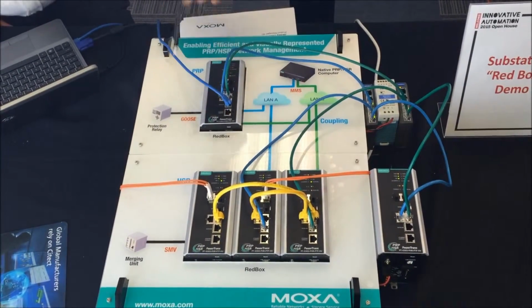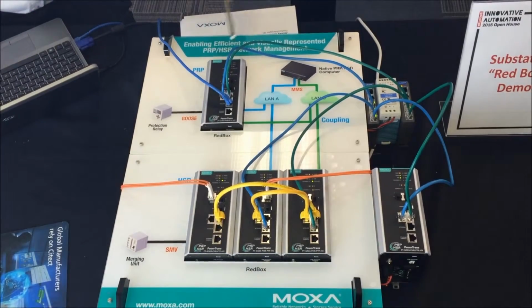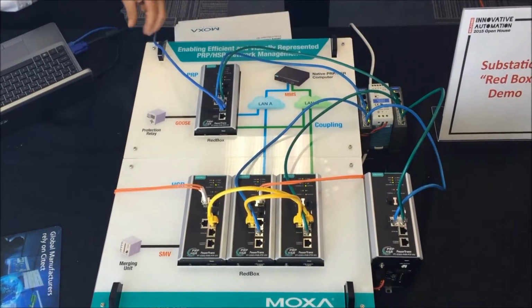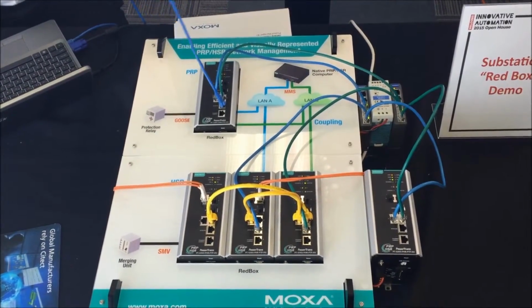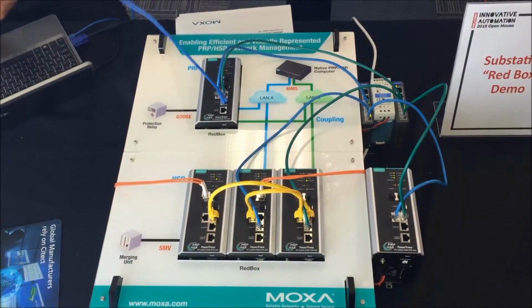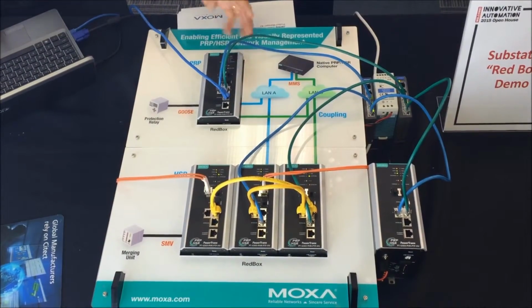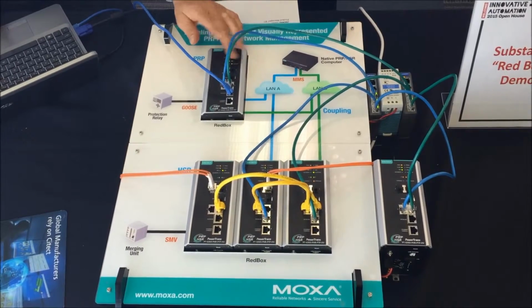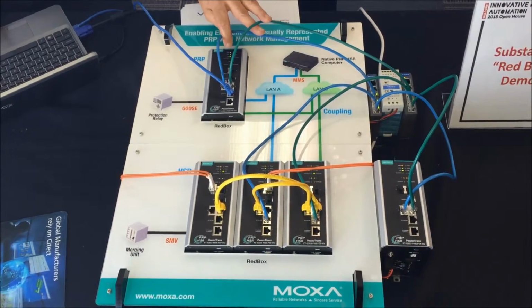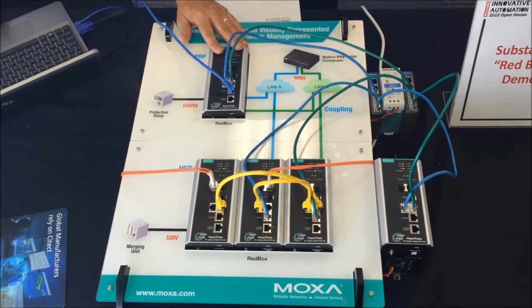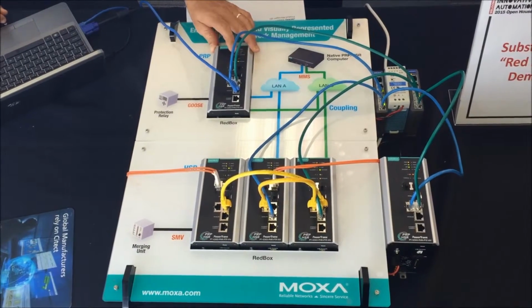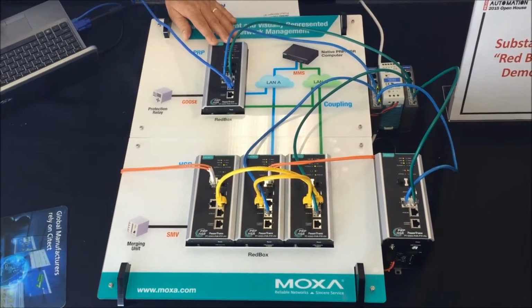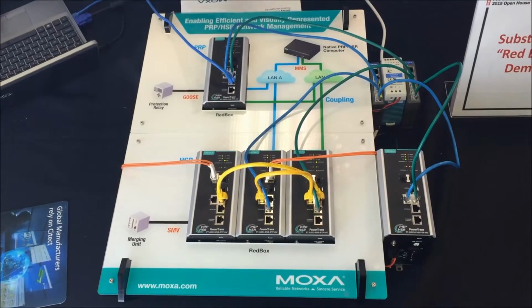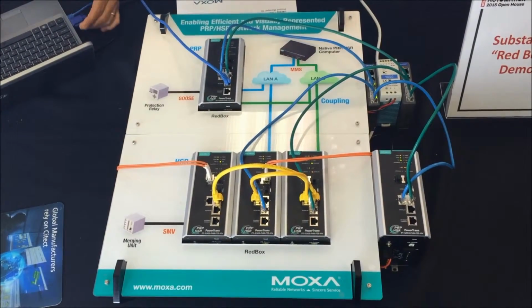One is a ring topology, the other is two parallel connections back to two networks to one device. So a device that has a single network interface is connected to two networks, and the failover occurs between these two networks seamlessly within this box. There is zero millisecond failover because each packet is sent in parallel across the network. One on the blue cable, one on the green cable.